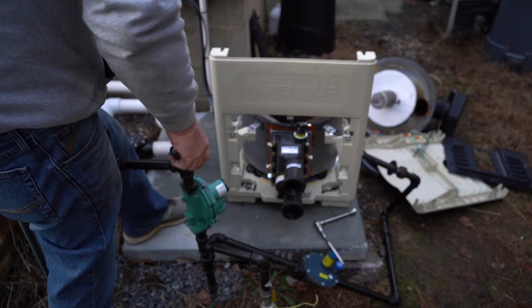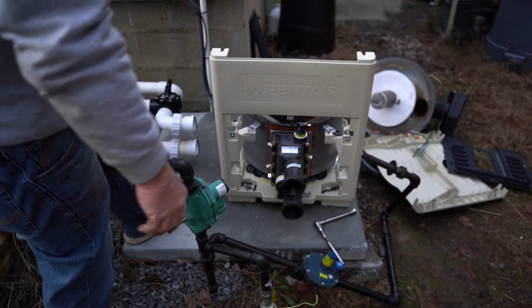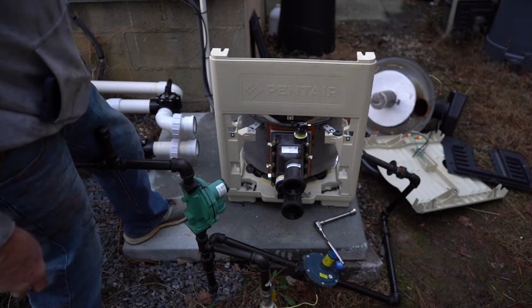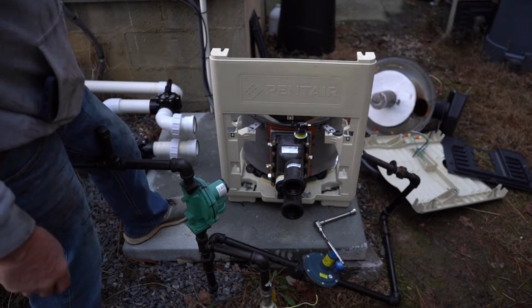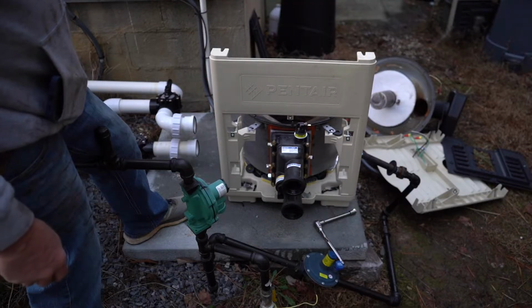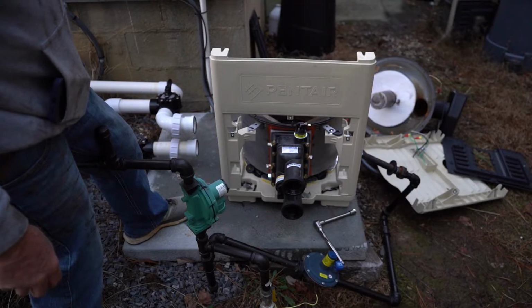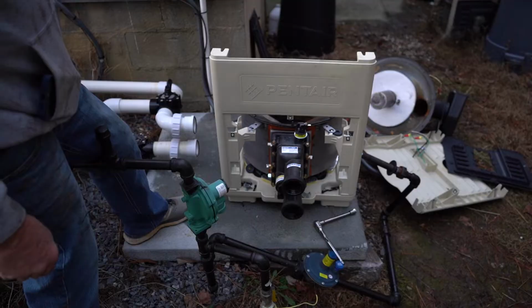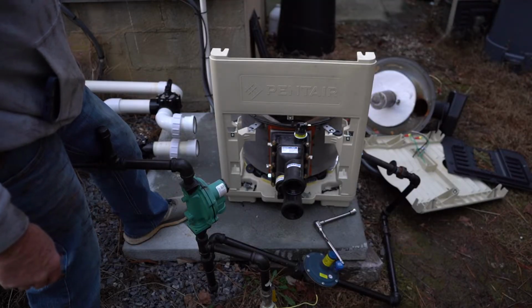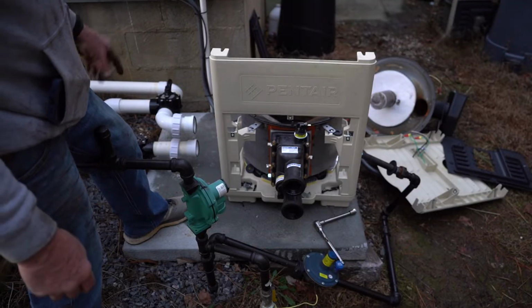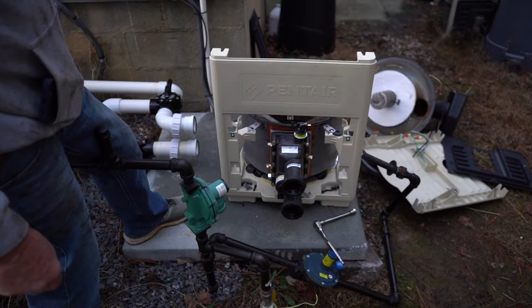So the reality is you don't have to tighten this very tight for it to seal. So don't kill it, because you're going to have to take that out again, since they corrode. They are replaceable. Typically Pentair recommends replacing the thermal regulator, the high limit, and the AGS every 2 to 3 years, depending on how much you use the heater.